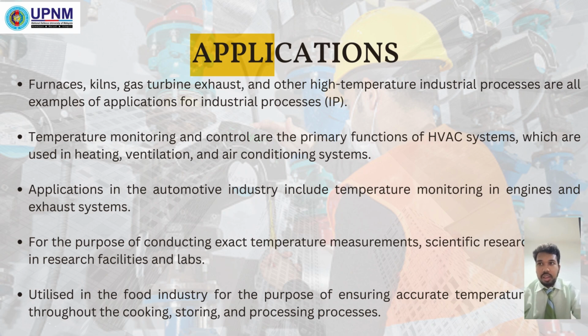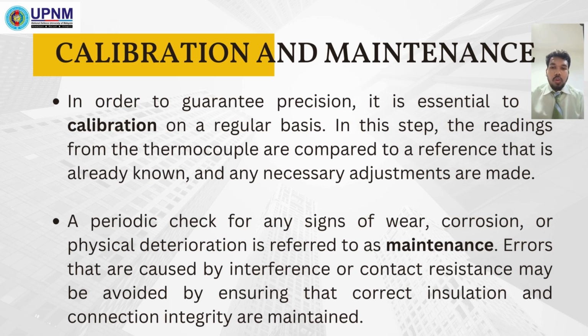The fourth one is scientific research. It's been used to measure in research laboratories and facilities. The last one is food industry. It's been used in food storing, food processing, and also food cooking processes. So how do we calibrate and maintain the thermocouple system? For the calibration, we regularly compare the thermocouple reading with a known reference and adjust the reading to ensure the accuracy. For the maintenance, we check the corrosion, the wear and physical deterioration, and also ensure the insulation and connection integrity to prevent errors from interference and contact resistance.